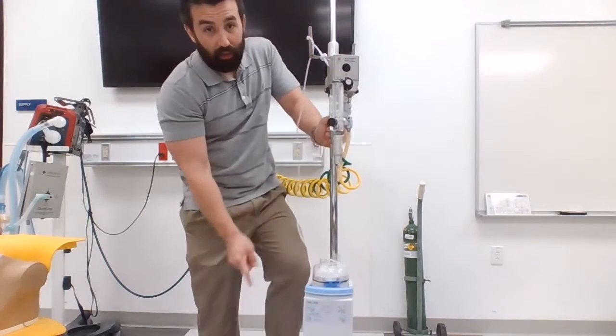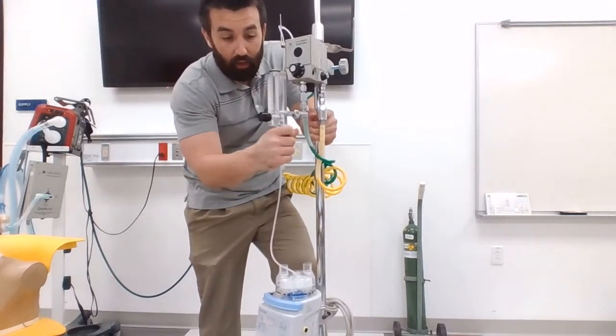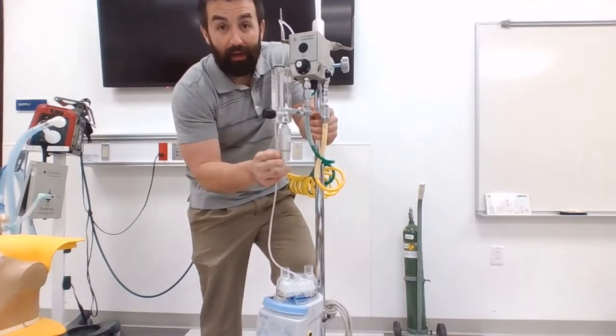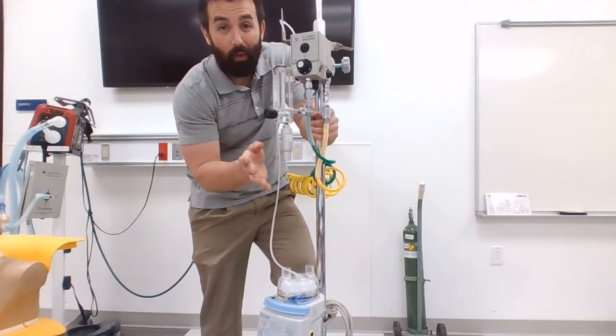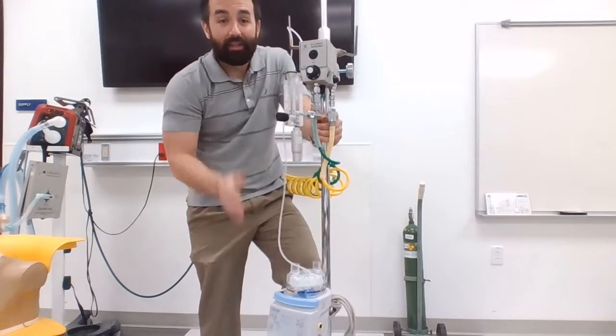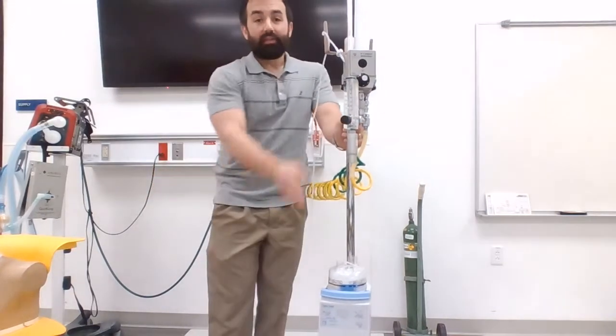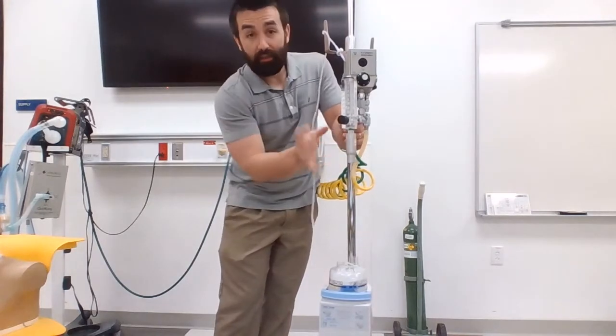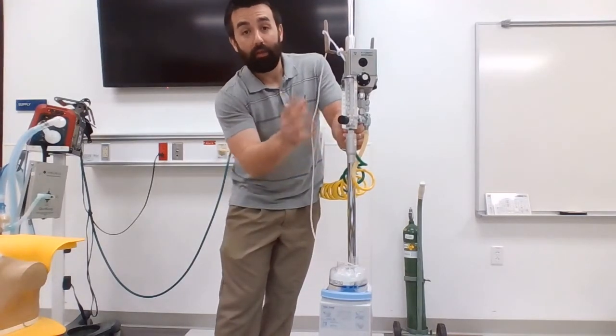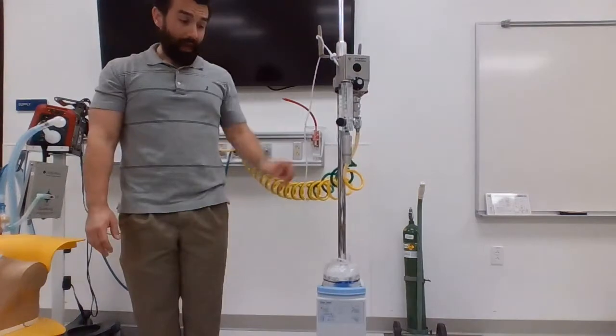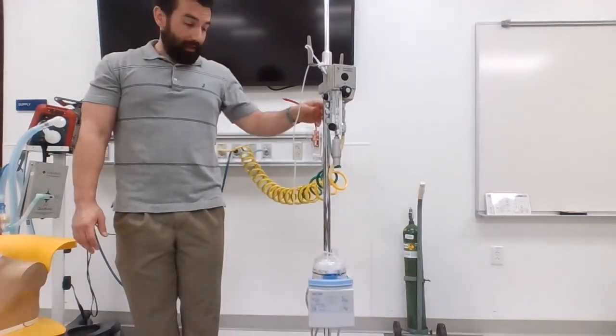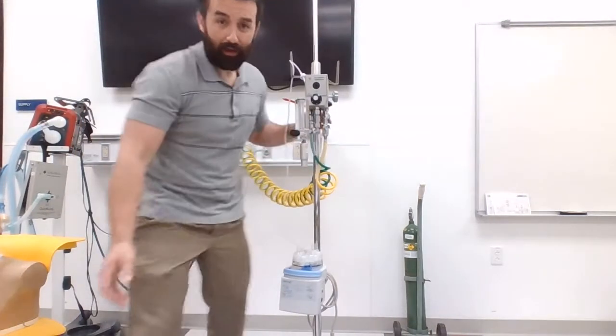Now, this flow meter looks a little bit different. As you can see, I have what's called a muffle adapter or a muffler on here. It makes 60 liters sound not quite as violently loud as if I didn't have this. So I have several of these, but that ultimately just threads onto the DISS adapter on the end of the flow meter there. As we get in, my tubing's pulling me further away, hang on.